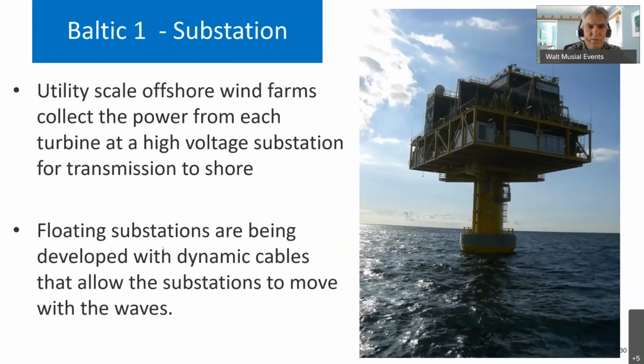Substations are necessary on larger machines. The voltages run in between the array cables, which generally generate and transmit current and power between the turbines to the substation, at about, nowadays, up to 66 kilovolts. It used to be half of that, but technology is advancing to higher voltages. Then it reaches the substation, and there's another step up to the export cable, where it's transmitted to shore.